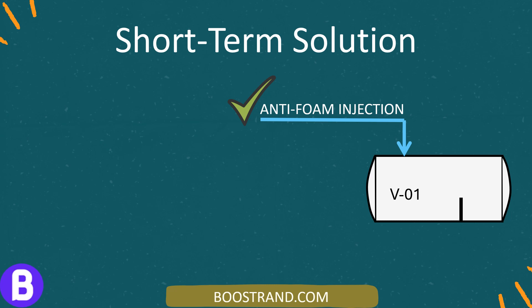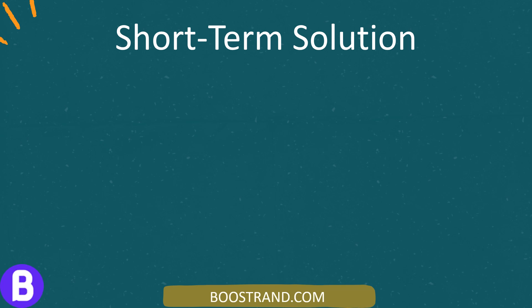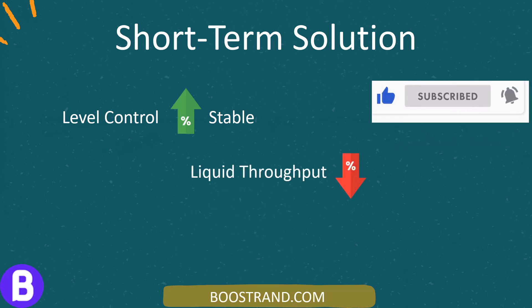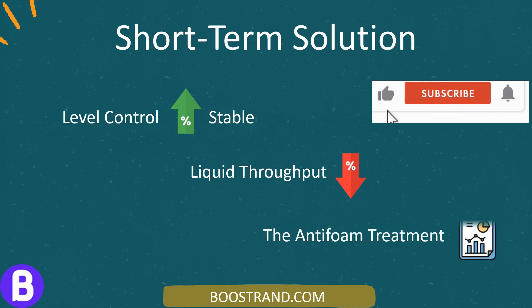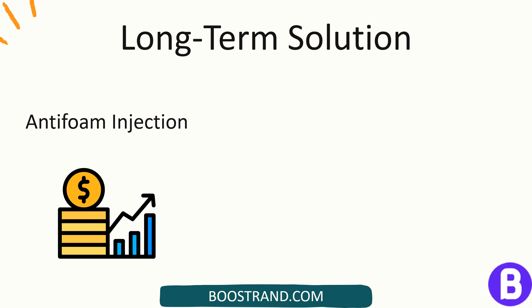Over the following weeks, the team fine-tuned the dosage and injection points of the anti-foam agent to optimize its effectiveness while managing operational costs. It was noticed that the level control in the separator was more stable, and the liquid throughput to the compressor suction scrubber was significantly reduced, illustrating the efficacy of the anti-foam treatment. However, it cost a lot — a continuous daily burden with a rental injection system in addition to the cost of the anti-foam itself.